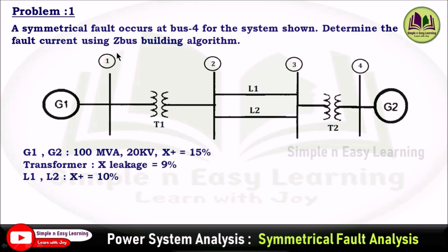In this video we are going to solve a problem in symmetrical fault analysis using the bus impedance matrix. Problem one: a symmetrical fault occurs at bus 4 for the given system. Determine the fault current using the Z-bus building algorithm. The system has 4 buses. Generator ratings: 100 MVA, 20 kV, reactance 15%. Transformer leakage reactance is 9% and line reactance is 10%.